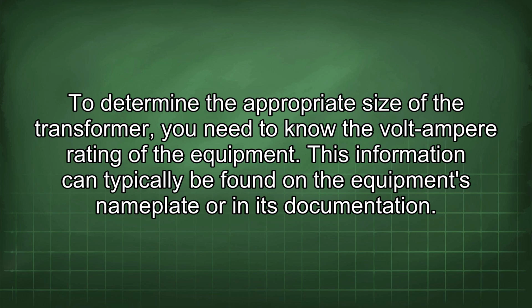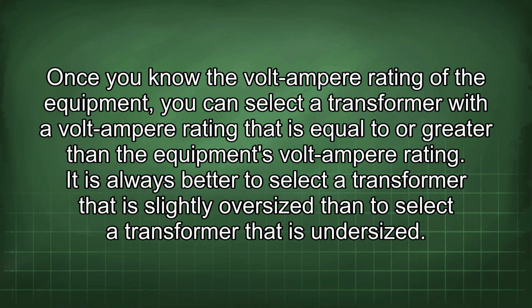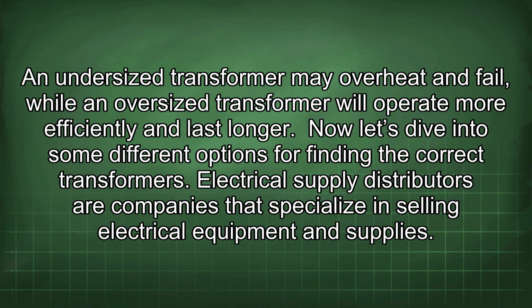This information can typically be found in the equipment's nameplate or in its documentation. Once you know the volt-ampere rating of the equipment, you can select a transformer with a volt-ampere rating that is equal to or greater than the equipment's volt-ampere rating. It is always better to select a transformer that is slightly oversized than to select a transformer that is undersized. An undersized transformer may overheat and fail, while an oversized transformer will operate more efficiently and last longer.